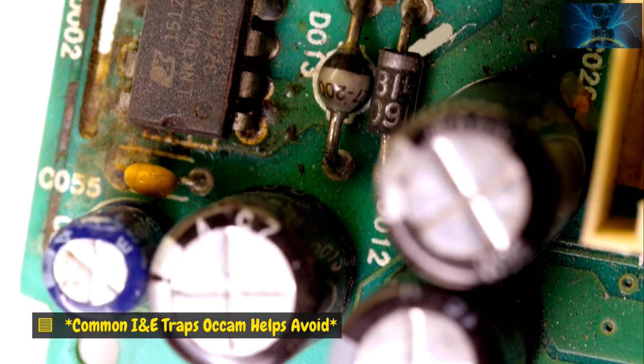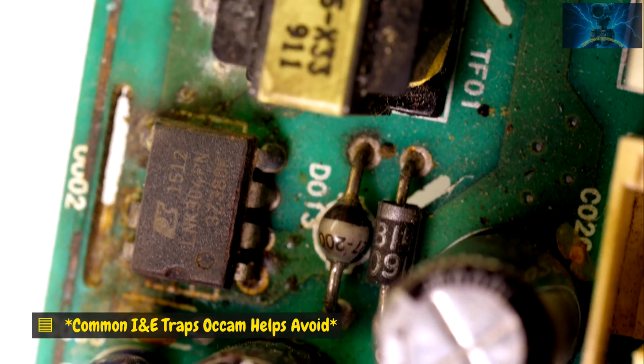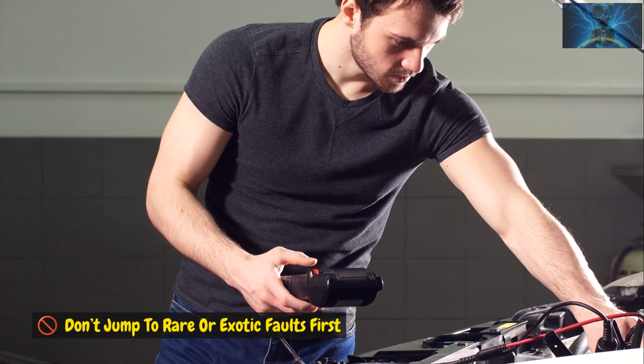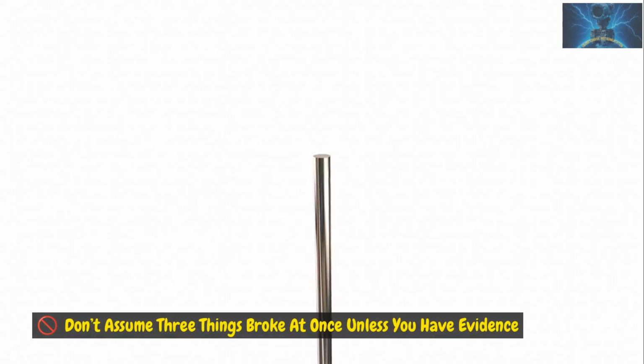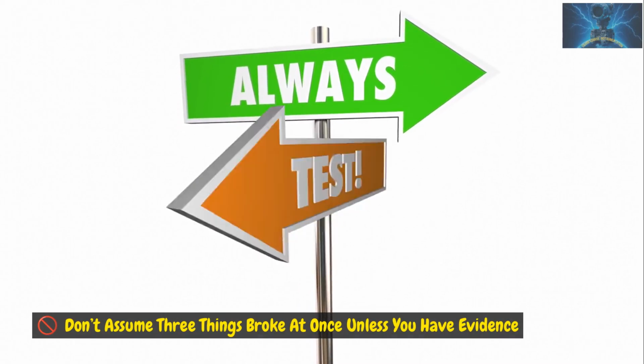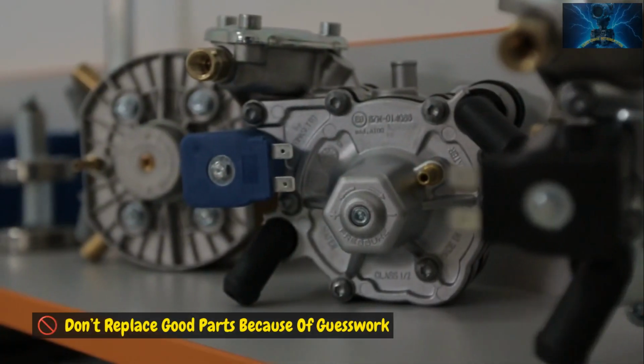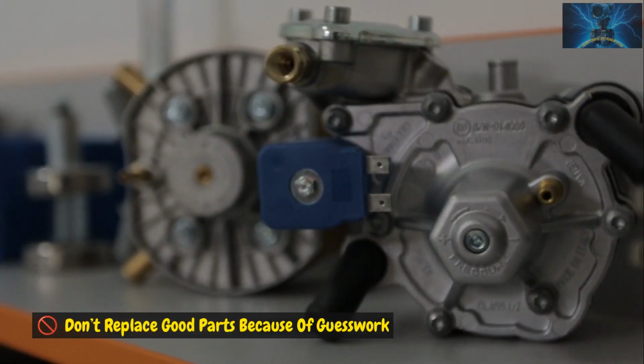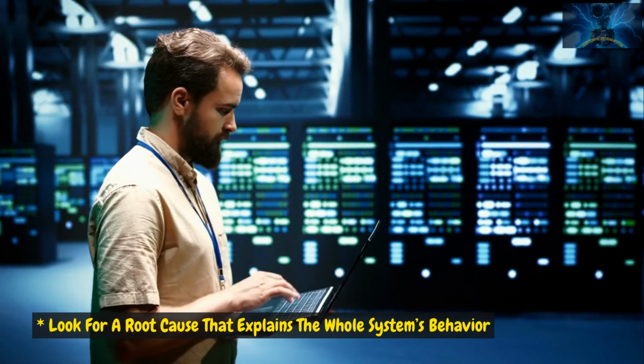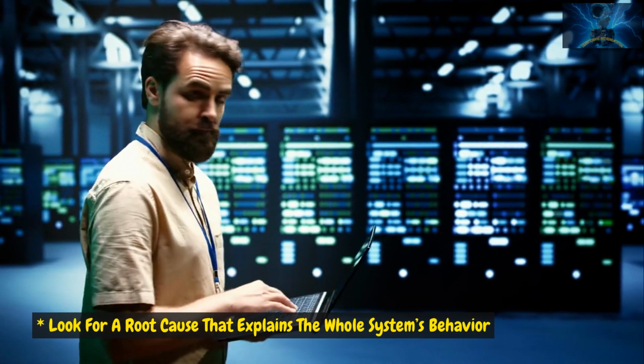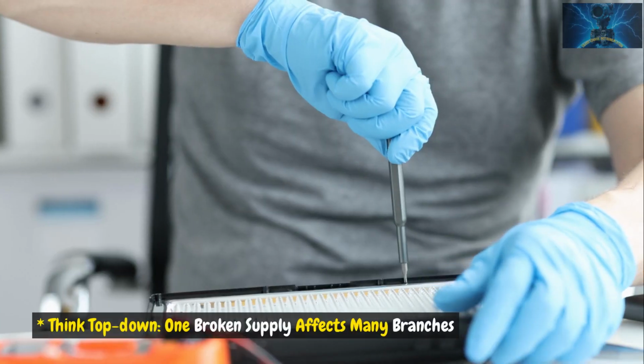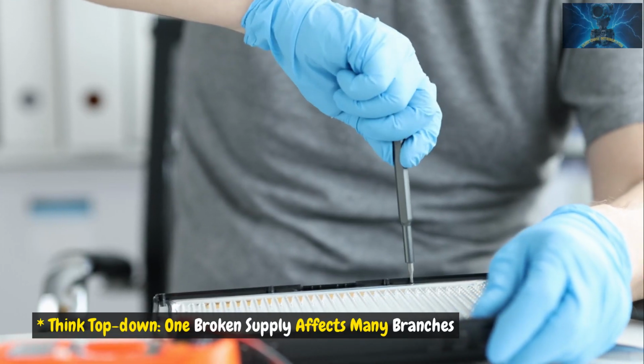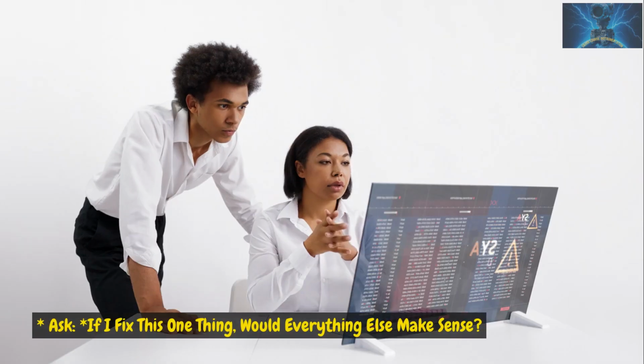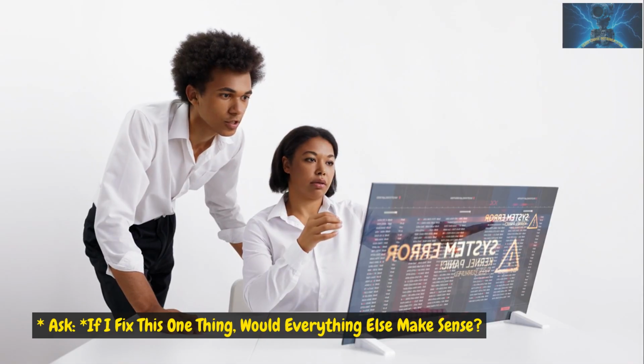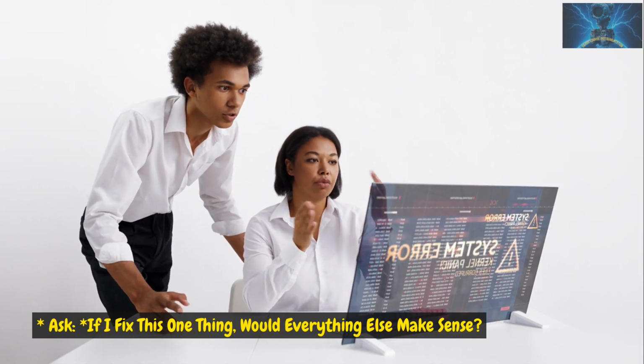Common I&E traps Occam helps avoid. Don't jump to rare or exotic faults first. Don't assume 3 things broke at once unless you have evidence. Don't replace good parts because of guesswork. Instead, look for a root cause that explains the whole system's behavior. Think top-down. One broken supply affects many branches. Ask, if I fix this one thing, would everything else make sense?